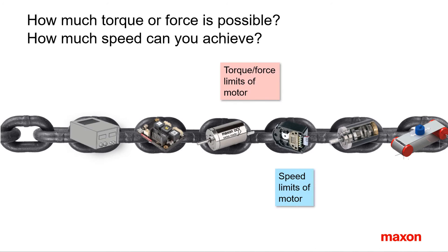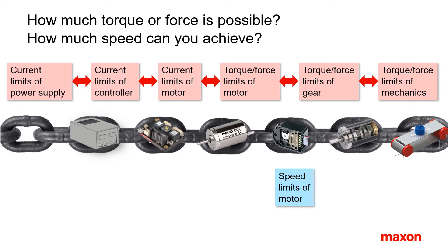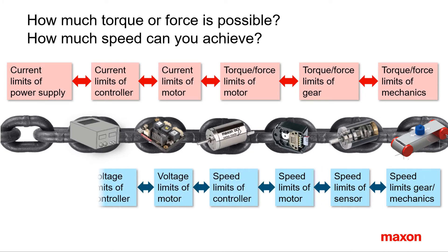The weakest link in the drive chain limits the power available at the load. Hence, it's not only the torque and speed limits of the motor — the limited torque capabilities of the gearhead or the mechanical system must be considered as well, or the current limit of the motor, controller or power supply. Similarly, the achievable speed can be limited by other components such as sensors, gears and mechanics, or the controller.